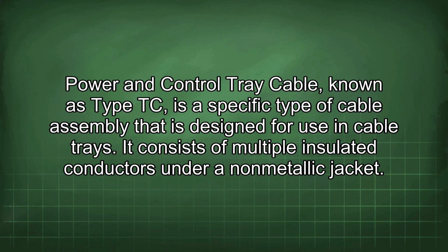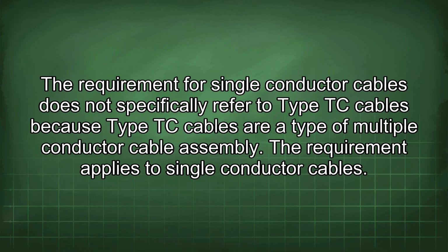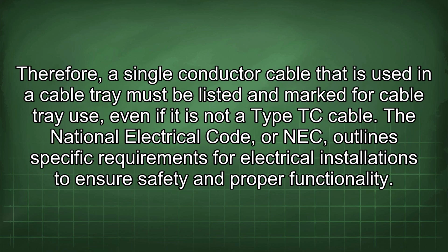Power and control tray cable, known as Type TC, is a specific type of cable assembly that is designed for use in cable trays. It consists of multiple insulated conductors under a non-metallic jacket. The requirement for single conductor cables does not specifically refer to Type TC cables because Type TC cables are a type of multiple conductor cable assembly. The requirement applies to single conductor cables. Therefore, a single conductor cable that is used in a cable tray must be listed and marked for cable tray use, even if it is not a Type TC cable.